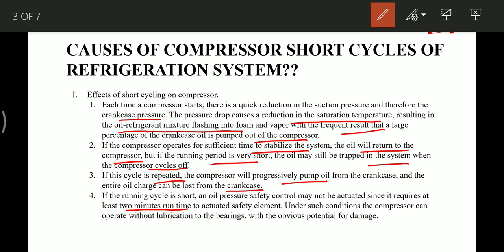If this compressor is running very frequently and short cycling, it will not let the safety oil pressure cutout activate. Under such conditions, the compressor will operate without lubrication of the bearing and it has a potential to damage the bearings.